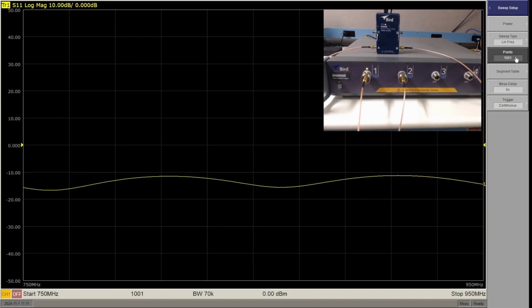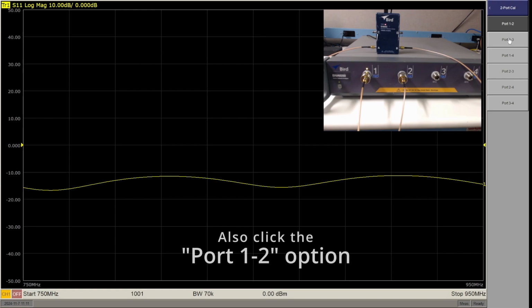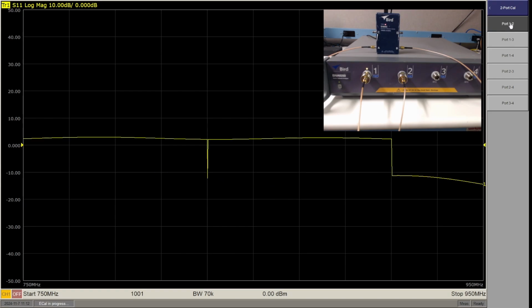Use the function buttons to navigate to the calibration choices where the ECal kit options are provided. Note that you do not need to specify a calibration kit since the software will communicate with the module to determine its model and capabilities. At this point, you will select two-port cal. This will immediately start the calibration process, detecting the port connections and orchestrating the internal device switching and measurements.